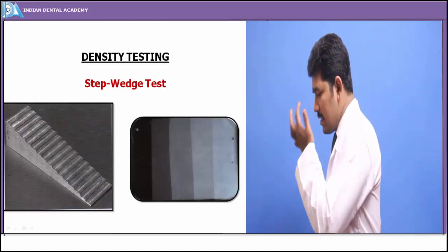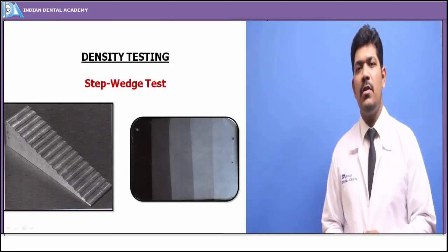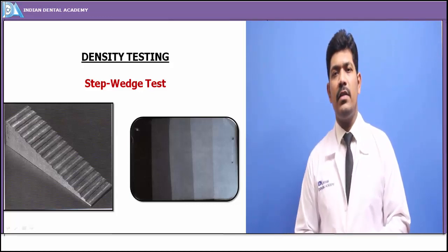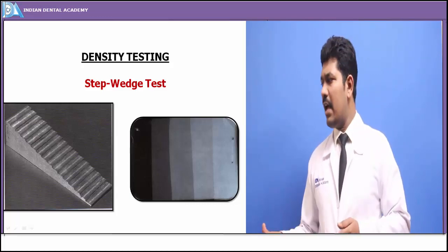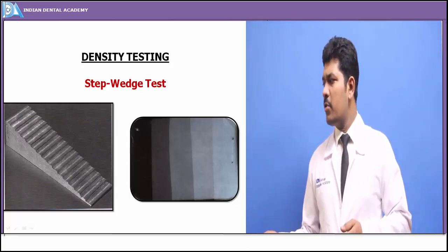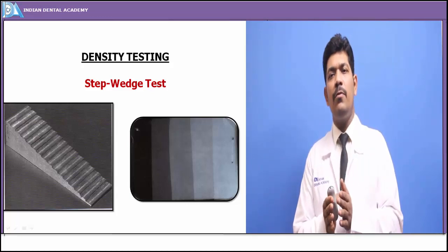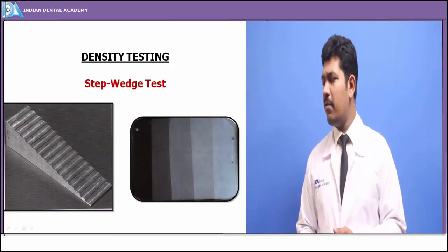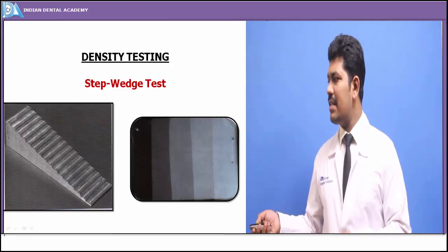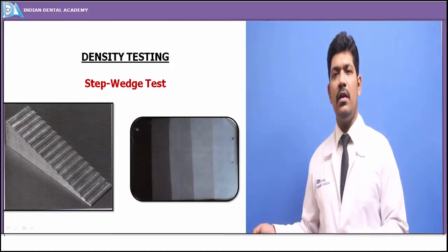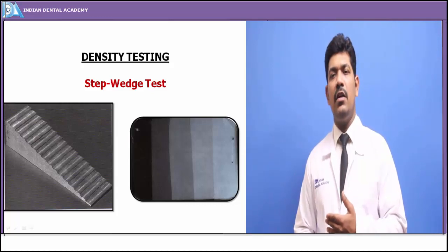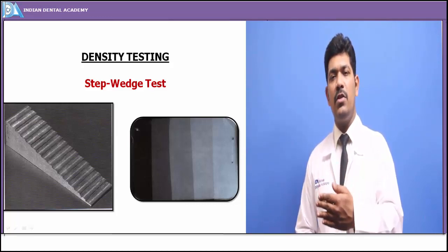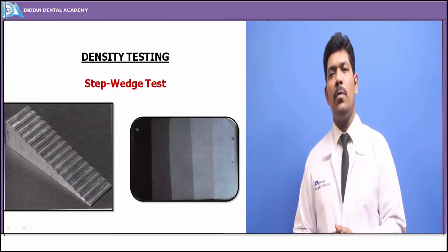For density testing, we normally use the step-wedge test, wherein a series of progressive lead foils are attached to each other. Progressively the amount of lead and attenuation is increased and then it is exposed onto a radiograph, which produces various degrees of darkening — showing us the amount of density needed to produce an optimal image.